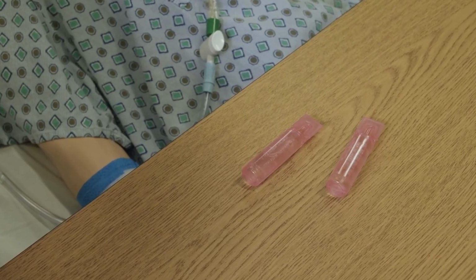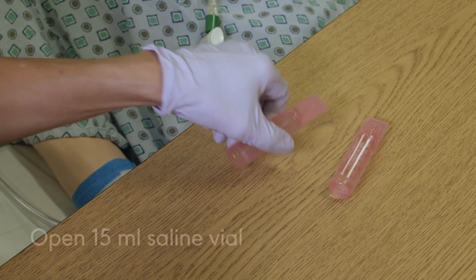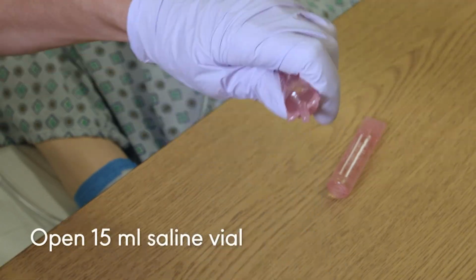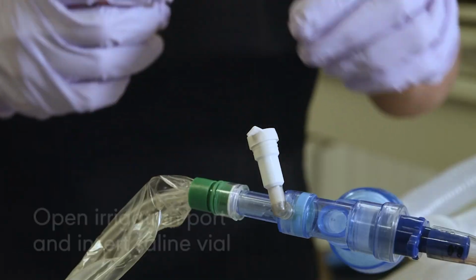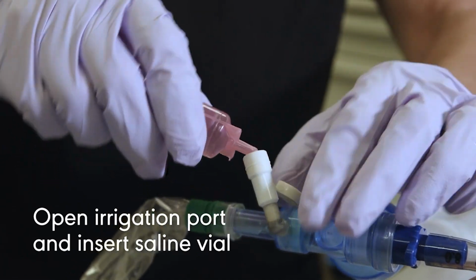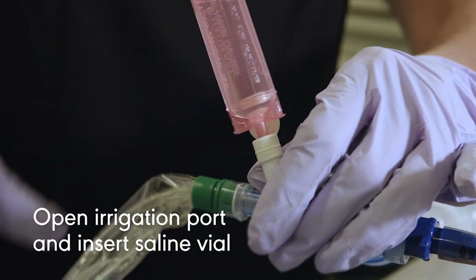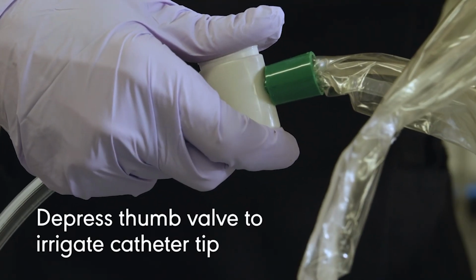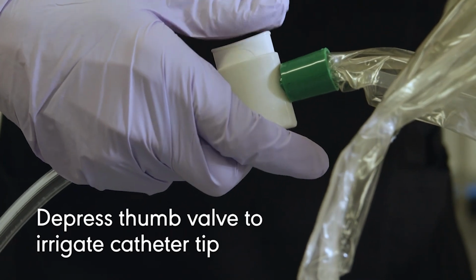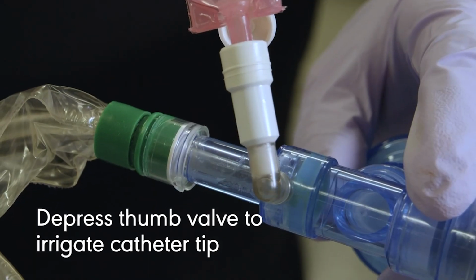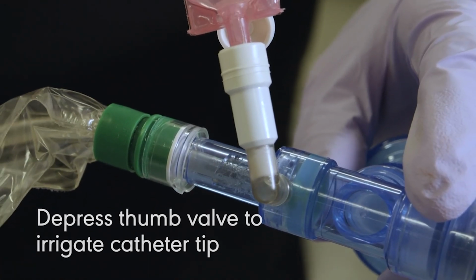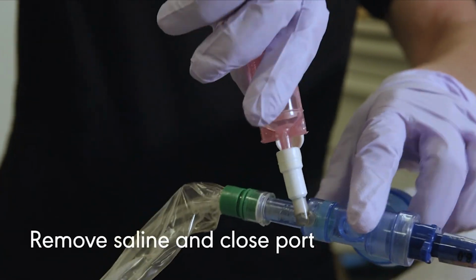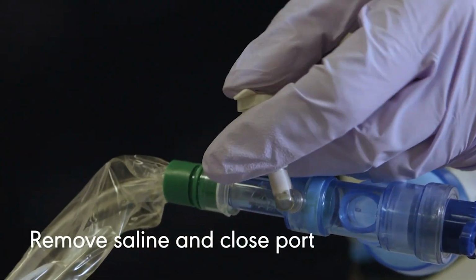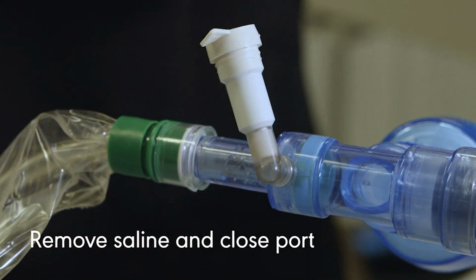Now you must irrigate the catheter tip. To do this, twist open a 15 ml saline vial. Open the cap on the irrigation port and insert the saline vial. Intermittently press and release the thumb valve until the catheter and chamber are clear or until the saline vial is empty. Remove the saline vial, discard it, and replace the cap on the irrigation port.